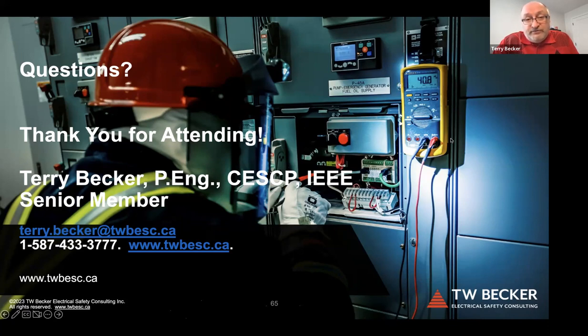So the limited approach boundary is 42 inches, restricted is 12, right? And limited approach, if I go inside the 42 and I don't breach the 12, I don't need shock PPE. It's only if I go inside restricted approach for shock that I need shock PPE. The arc flash boundary is a separate distance, and it's a variable distance depending again on the electrical equipment parameters. So that's a variable distance. And then there's another distance for arc flash called the working distance. And the working distance is really the distance from where the abnormal arcing fault would occur to the worker's face and torso.